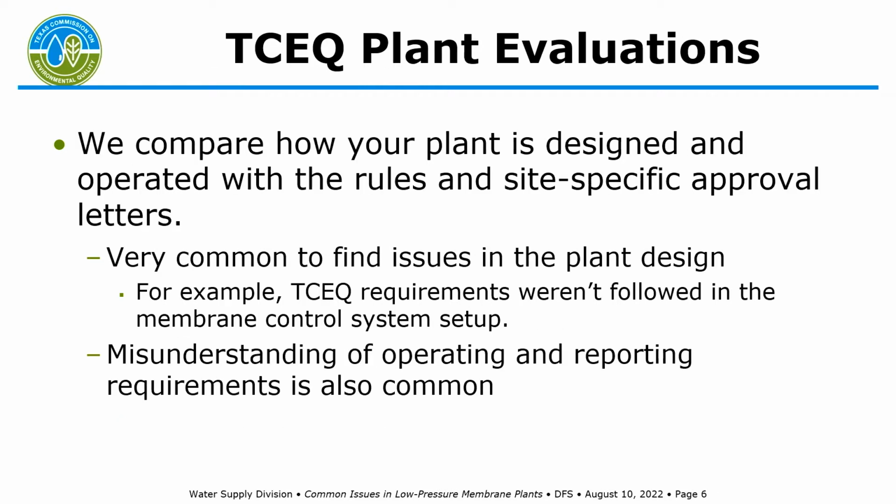So during a TCEQ plant evaluation, we take those approval letters and some of the rules that do cover low-pressure membranes, and we compare it to your plant to see if everything's matching. I will say it's very common to find issues in membrane plant design. I'll give you an example here.